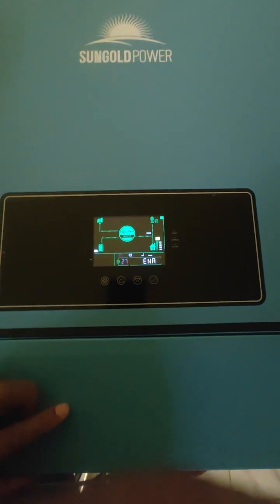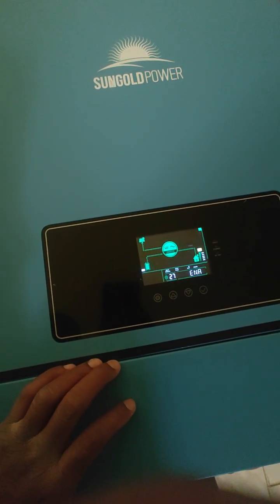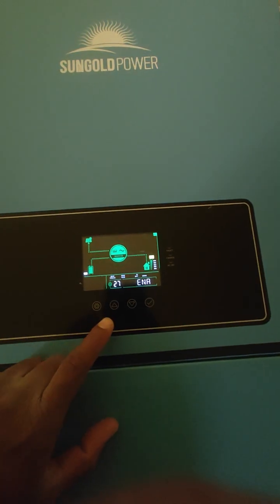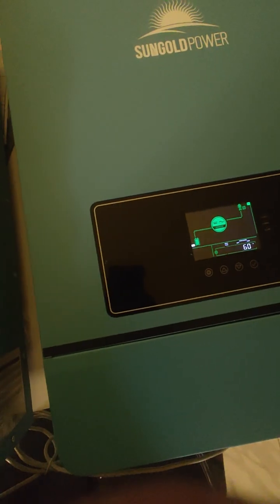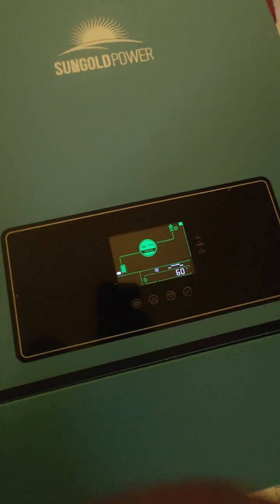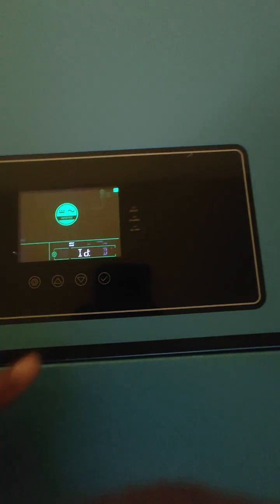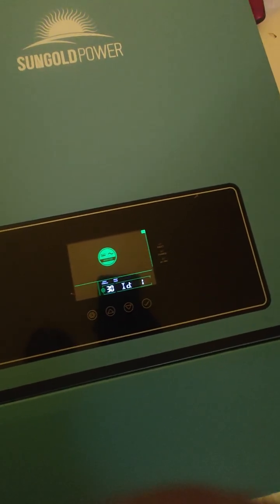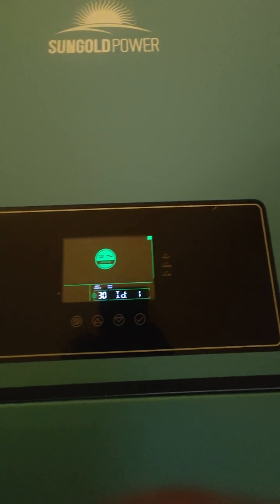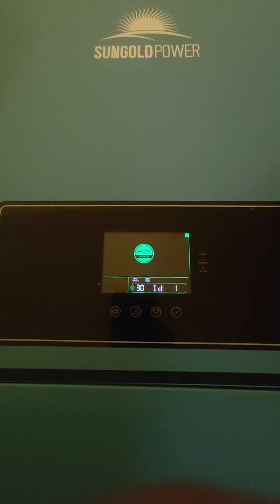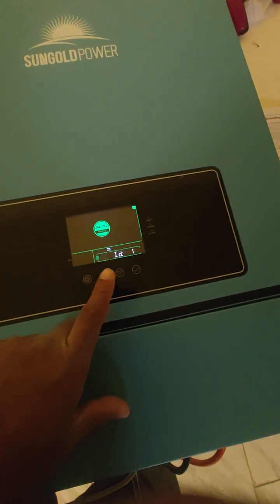26 power source switching reminder. Enable is fine. 27 inverter overload switch to bypass. I guess that's fine. 28 is the max utility charging current. 60 is the default, so we're going to keep it there. 30, the RS485 address. Number 1 is good because this is a single inverter. If we had 2, we would change that. 31. There is no 31 on this manual, so I guess I'll skip it.